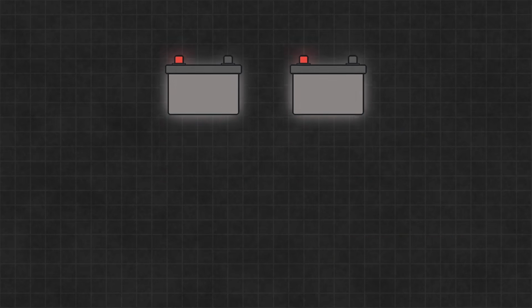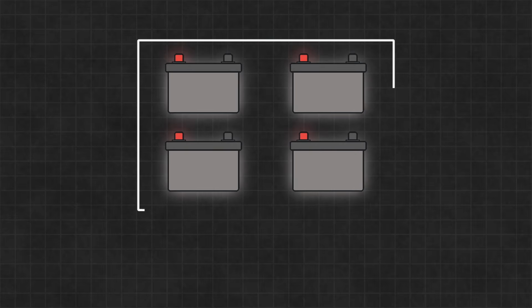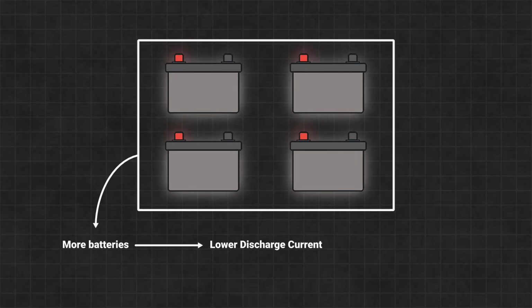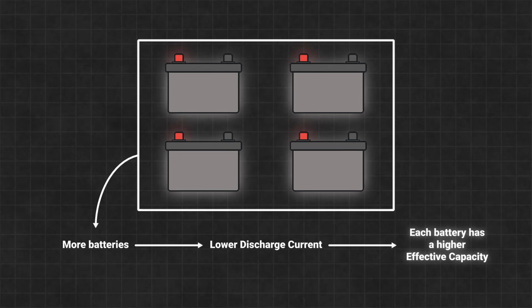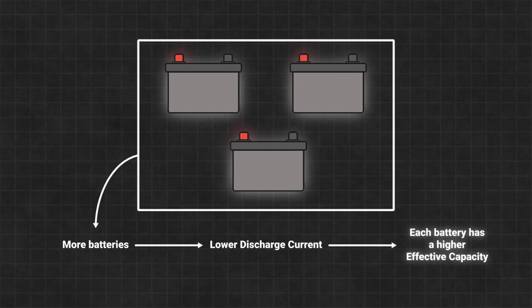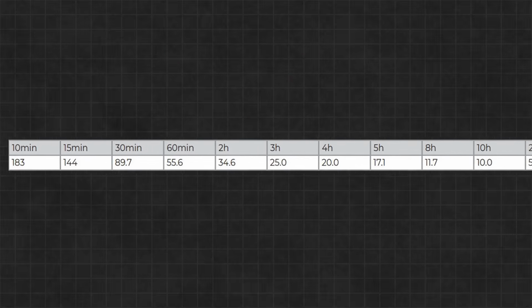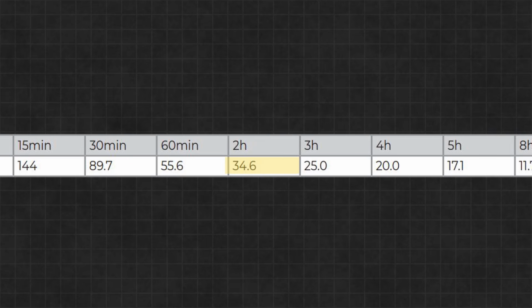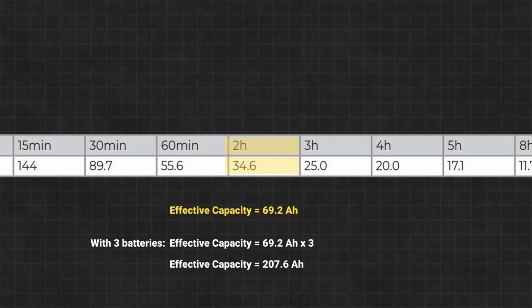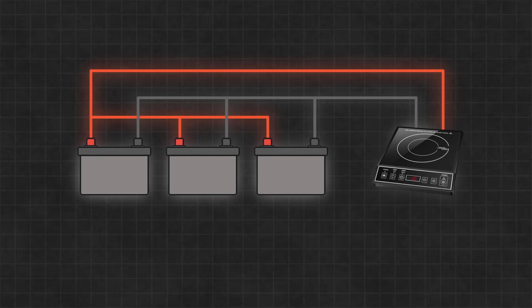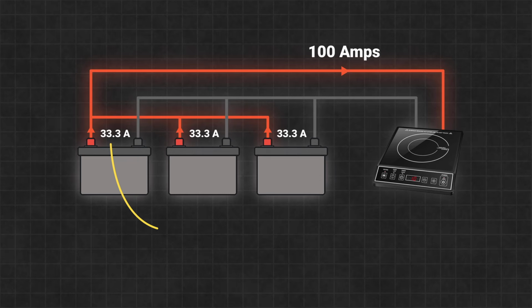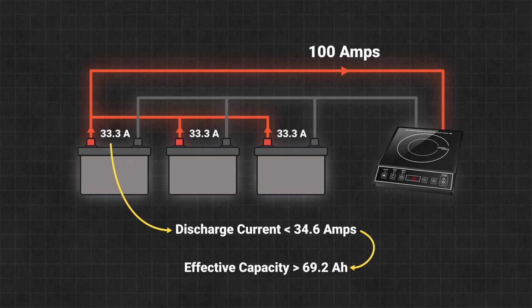The first instinct might be to just add 2 more batteries to double the size of the battery bank. However, the more batteries you add, the lower the discharge current on each battery will be, which in turn means more effective capacity. So if we really want to optimize for cost and avoid oversizing, we might be able to get away with just 3 batteries instead of 4. For example, based on the same table, at a discharge current of 34.6 amps, each battery would last 2 hours, which means an effective capacity of 69.2 amp hours per battery. With 3 batteries, that gives us 207.6 amp hours of effective capacity. And since the 100 amp load is now shared between the 3 batteries, each one would only need to provide 33.3 amps, which is lower than 34.6, so we can expect a little bit more than the effective capacity we just calculated.